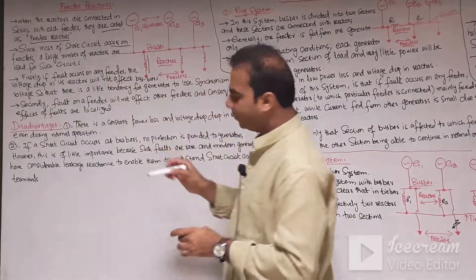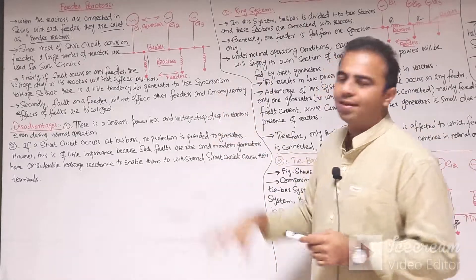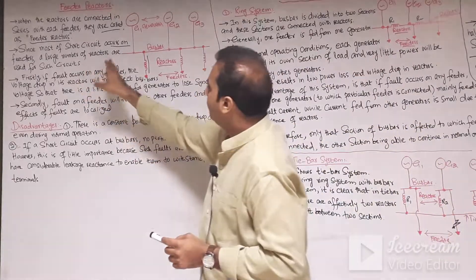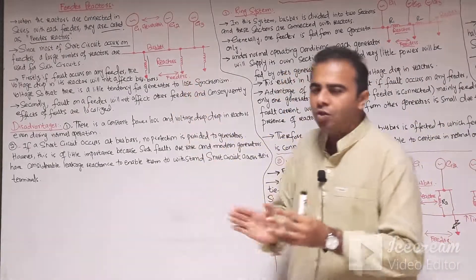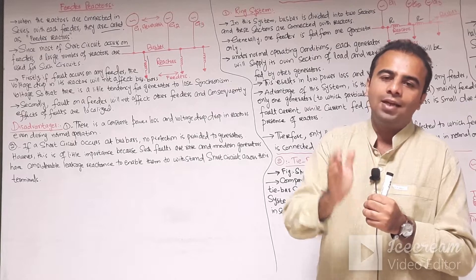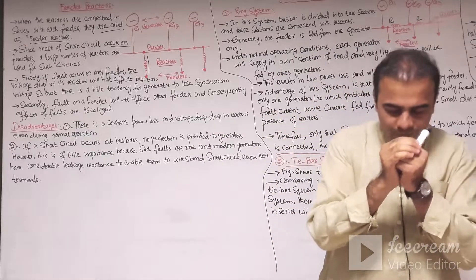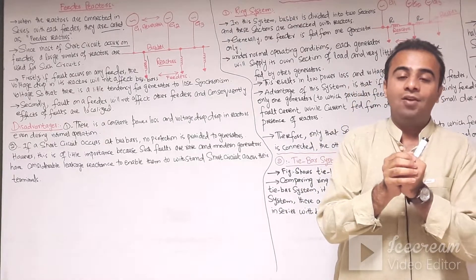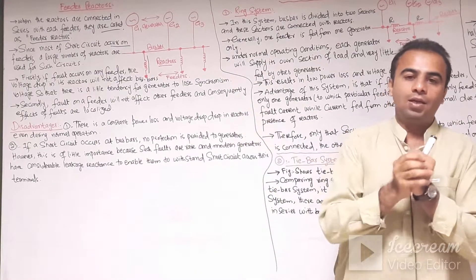Since most short circuits occur on the feeder because loads are connected to the feeders, most faults in the power system occur on the feeder side. A large number of reactors are used for such circuits — the reactors connected in series with the particular feeder limit the short circuit current so that circuit breakers connected with the particular feeder can withstand the amount of short circuit current, because the reactors provide additional reactance to that particular feeder.